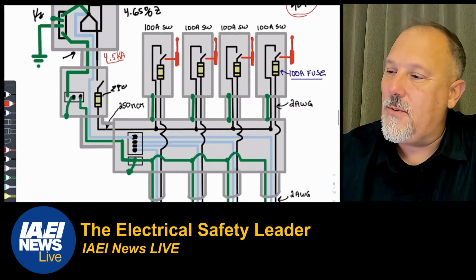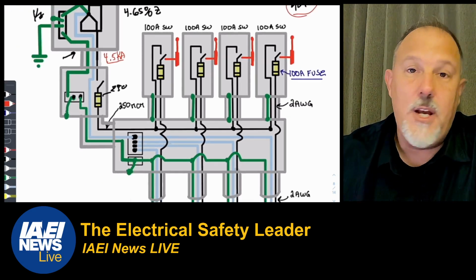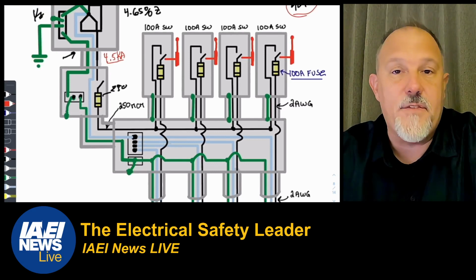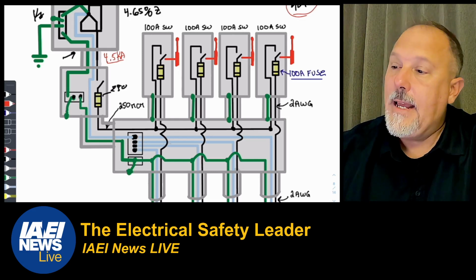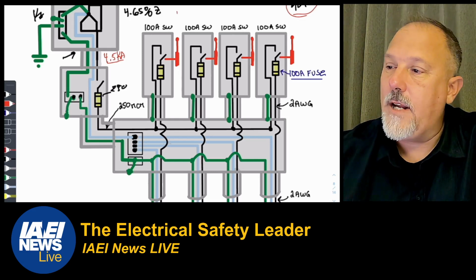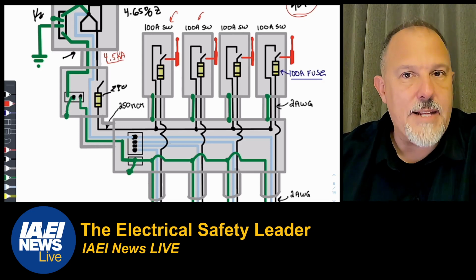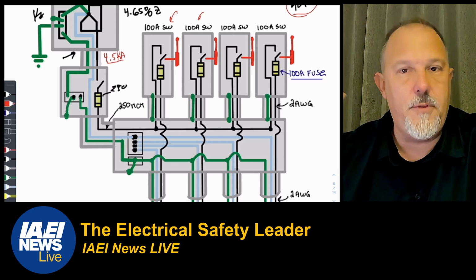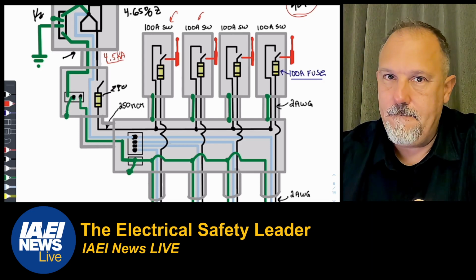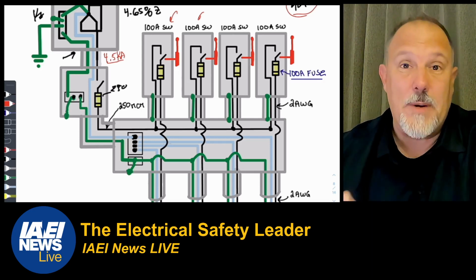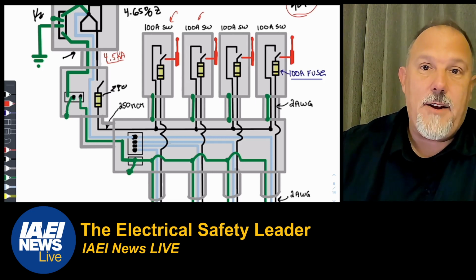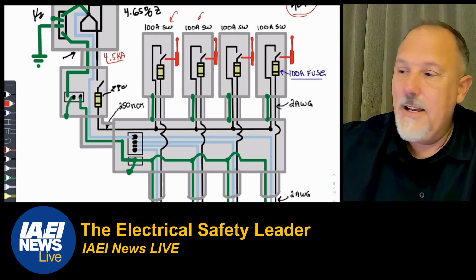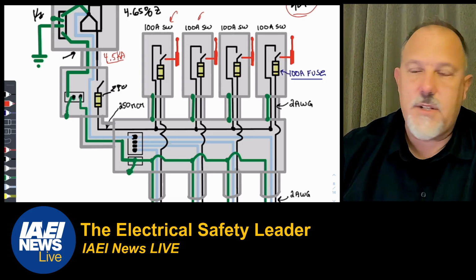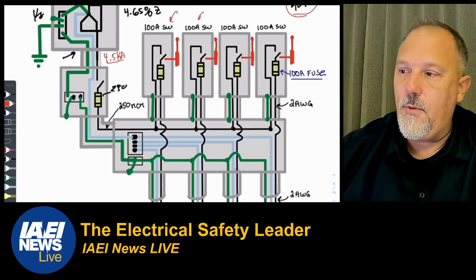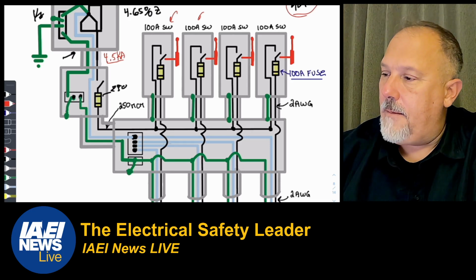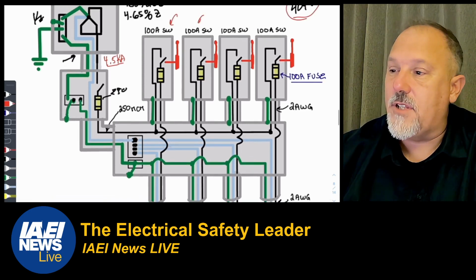So I tell you what, pulling that neutral up into each of these switches, we came to the conclusion that you do not have to pull that neutral, that grounded conductor, into each of these 100 amp switches. Just pulling that switch leg up there, those two conductors through those two fuses, is all you need to do, because that neutral is not going to do anything anyway. You're not doing anything with it, and you're not going to put a light switch there. The requirement back in 404 is for light switches. It's not a 230. These aren't service devices. So you don't need that neutral.